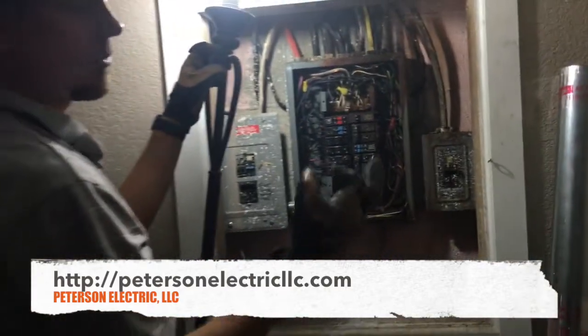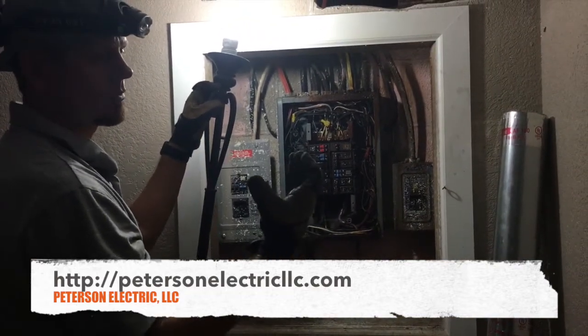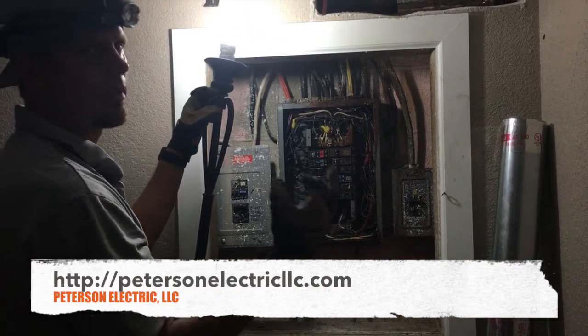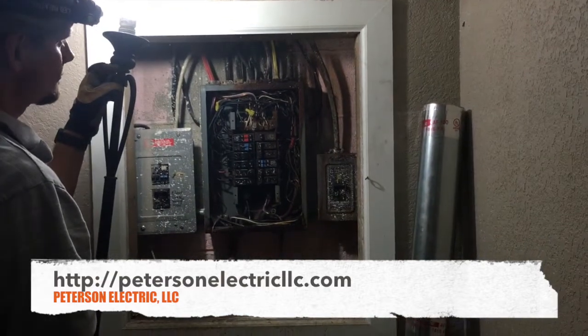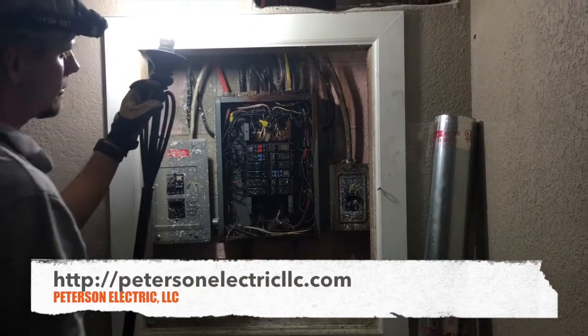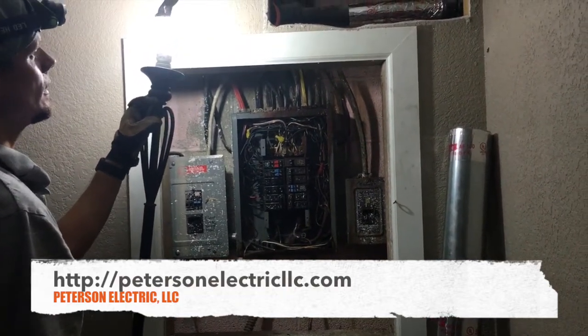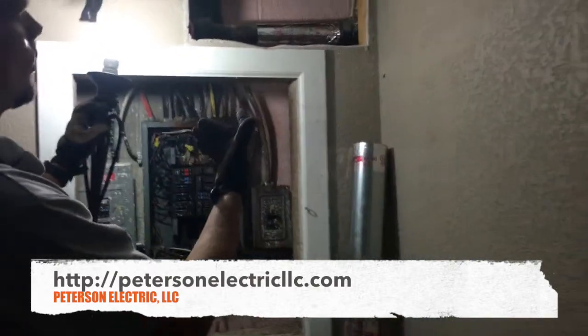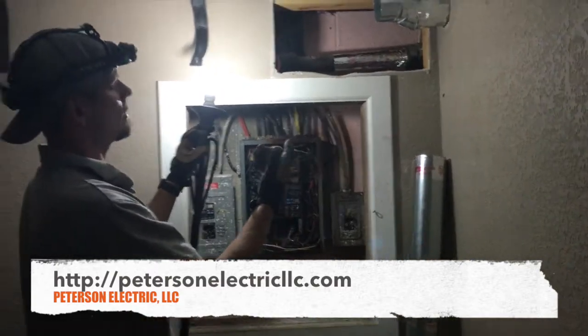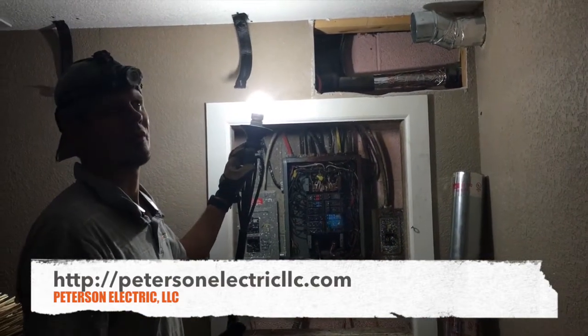The service is so small that the service riser mast is an inch, not 2-inch GRC. It's a 1-inch EMT. She's got breakers shorting now. That's the complaint. And in order to service this, the code says there should be no water, no plumbing, no drainage, any line above the electrical panel. But that's typically commercial, and that's in 110.26.